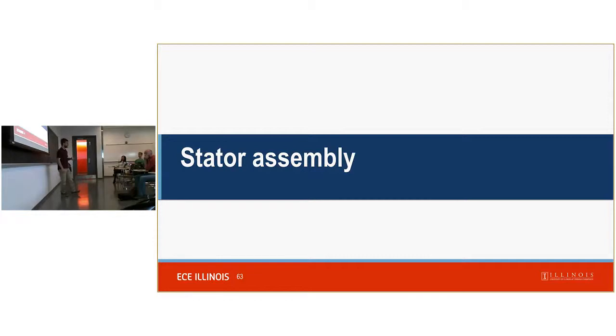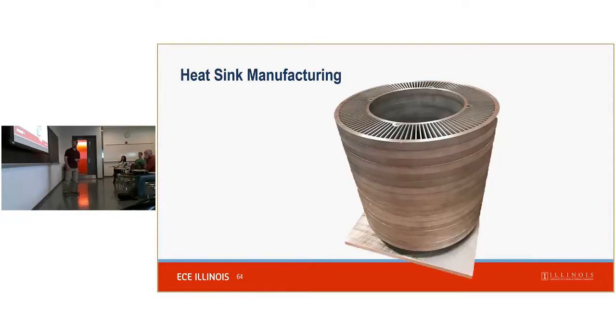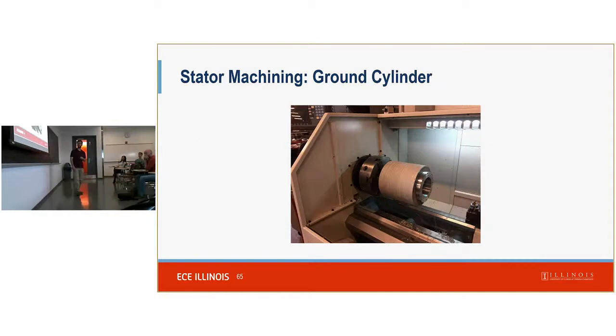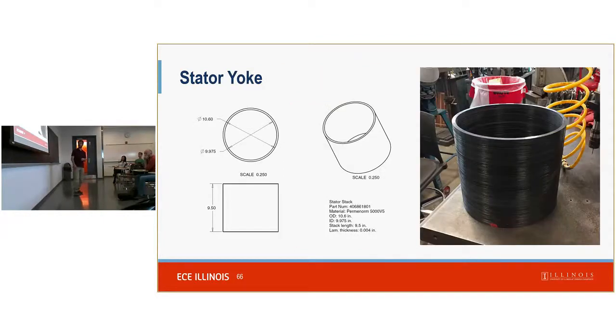So the next category is assembly of the stator. A year ago, at the last annual review, the heat sink was just about completed. And these are stacked up pieces that were wire EDM'd, so very accurately machined, and that was joined together. The ground cylinder is the piece that goes inside of that, and the bearing has the bearing housings. That was assembled. And then we received the stator yoke. That's the cobalt iron that is part of the magnetic circuit. That's an active part of the machine.